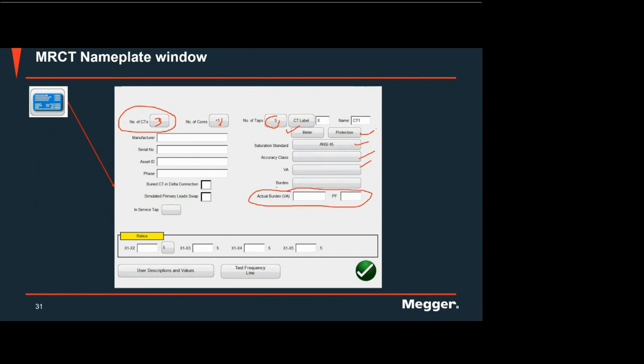Remember, as I've shown you a while ago, we have this table, right? So if the VA is not there, maybe you are looking at a different VA, maybe you are looking at the actual burden, then you can put the actual burden here, maybe 0.1 VA at 0.9 power factor or 1 power factor, then it will display automatically in the test result. Even if you have done the test already, you can put the value here, and then in the report it will change automatically. So you can put the ratio here if you don't want to do the estimate, right?